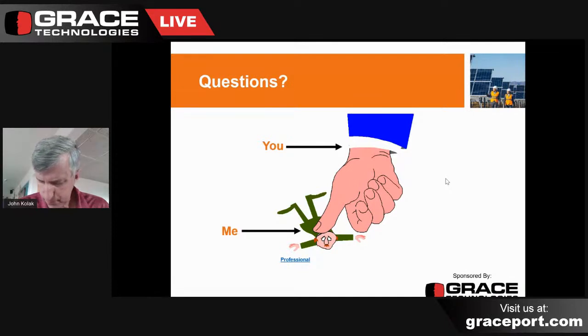Thanks, John. So the next one is, how did you come up with 1.1 times for full fault current in PV systems? Just take a look at the actual nameplate of the array itself, or the panel itself, and it'll give you the normal current rating and then the fault current on the same panel, and you'll notice it calculates to about 1.1 what the normal current output is, and that can be extrapolated to the whole farm. Everything will be about 1.1 of what full load is.